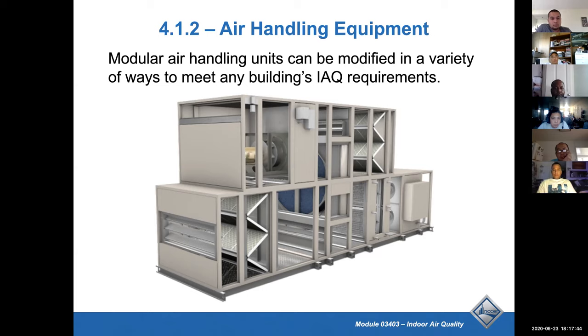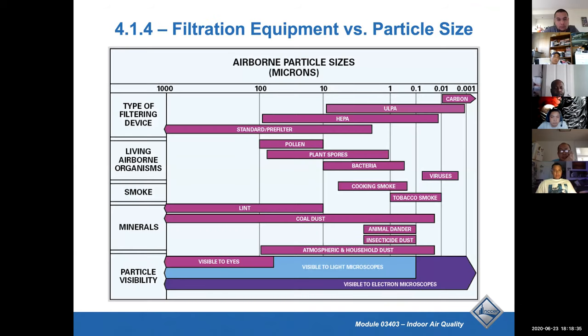Modular air equipment. They didn't have this back in the day. Most equipment in a building was installed and made to last for many, many years and just be rebuilt. Now you have modular systems, and even the U.S. Navy is going modular on their ships because they can take a whole module out and just replace it instead of working on the equipment. It's a more effective way of doing maintenance. They have some modular air conditioning that replaces chillers.